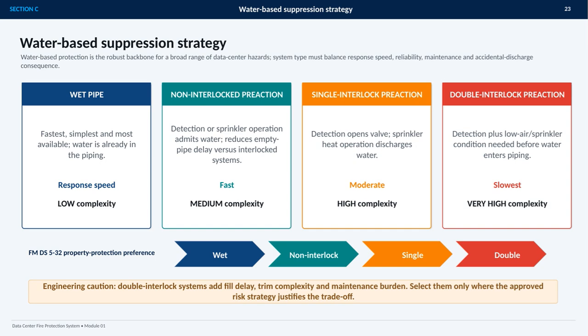Wet pipe is the fastest and simplest option, because the piping is already filled with water. It has low complexity and the greatest immediate readiness. Non-interlocked preaction is also fast, admitting water when detection or sprinkler operation occurs, and it reduces the empty pipe delay associated with more restrictive arrangements.